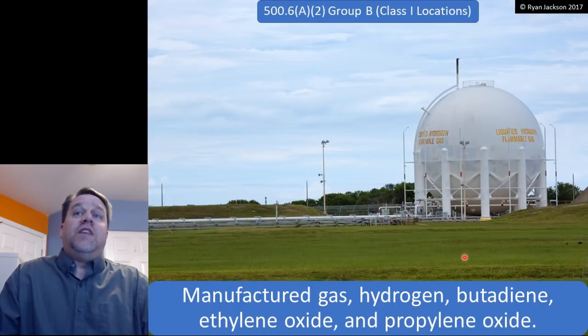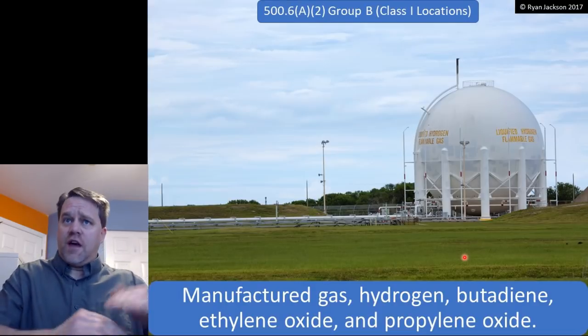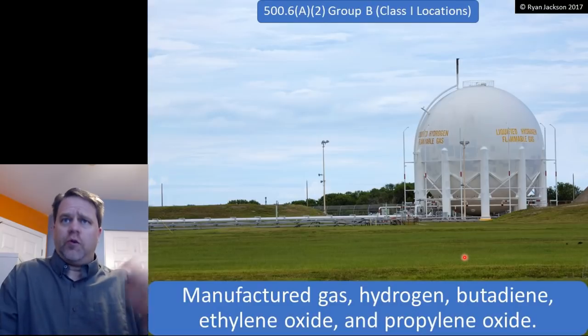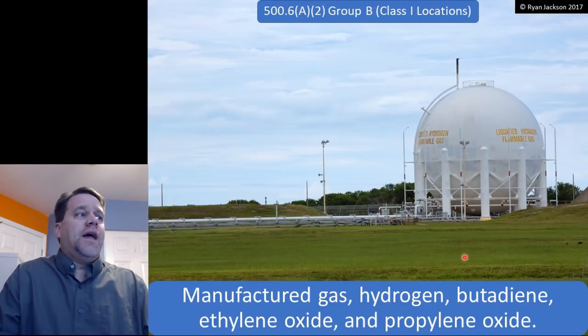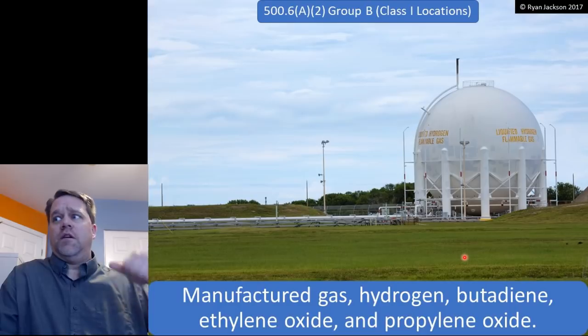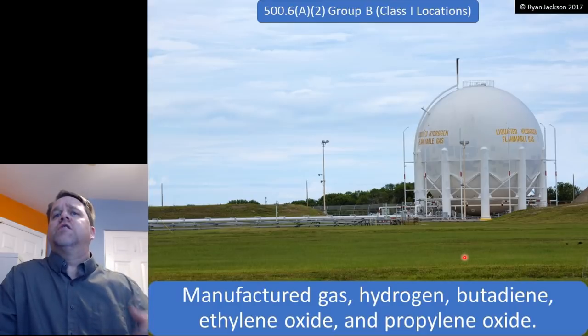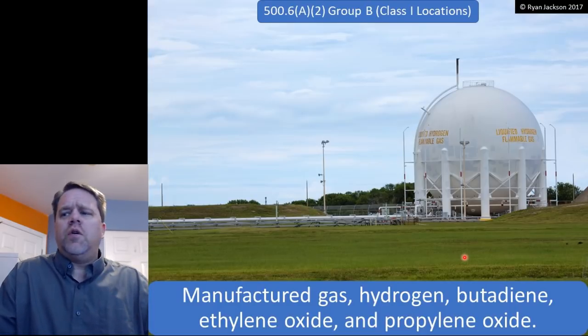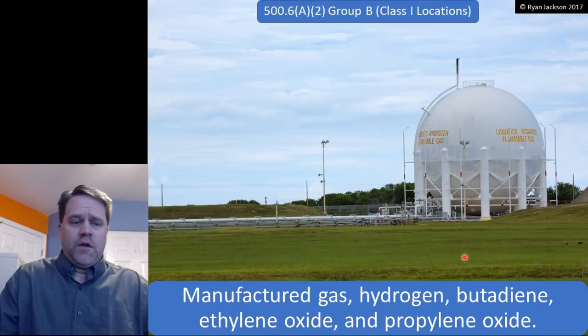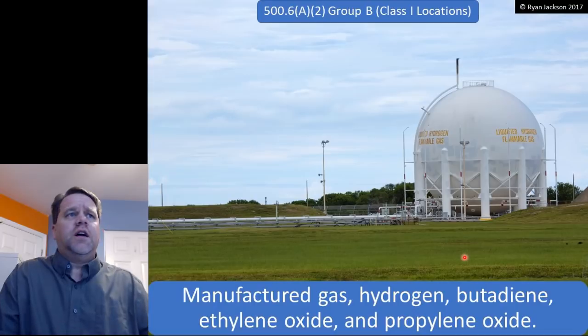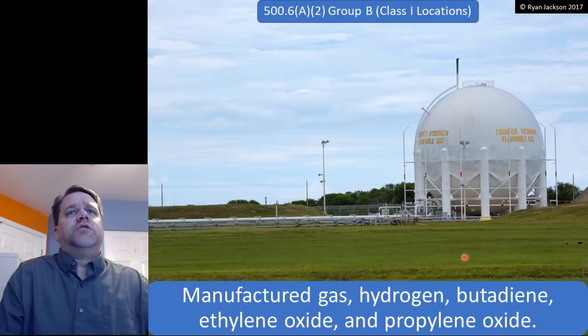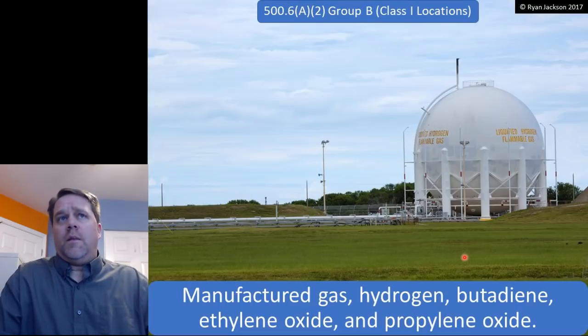If you have the NEC handbook, there's a nice big table in there that gives you the group ratings of different compounds and the explosive limits and vapor densities and auto-ignition temperatures and everything else. Or you can get literature from Crouse-Hinds or from Appleton. They each have a code digest that you can get, and they have all of this information for you as well. Group B is not particularly common.